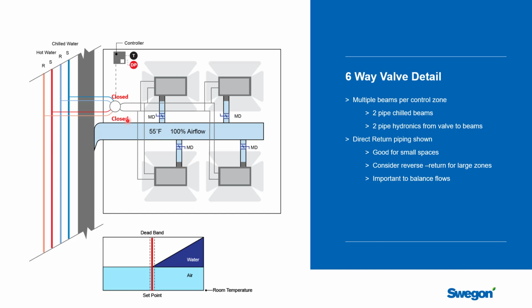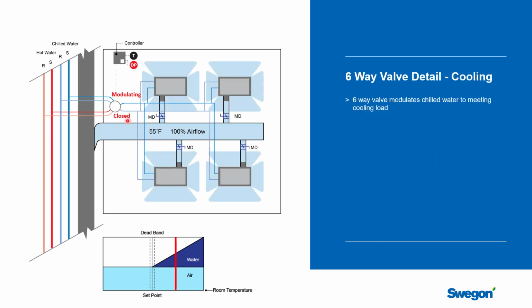So right now the system is neutral. Let's shift it into a cooling load. The heat load is raised in the space, and the way the valve responds is that the controller sees that through the temperature sensor, and it modulates the valve into its cooling mode and allows chilled water to flow out to all the beams to meet the cooling load.